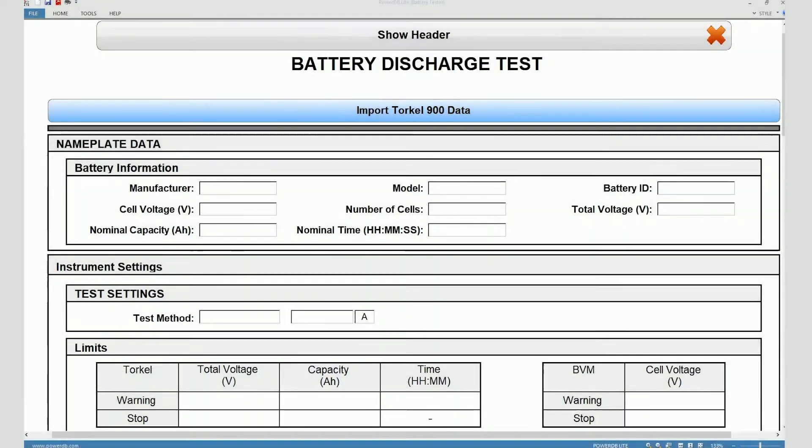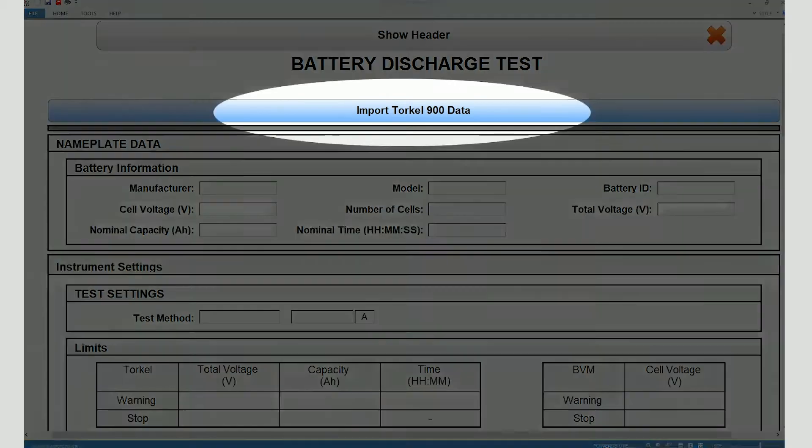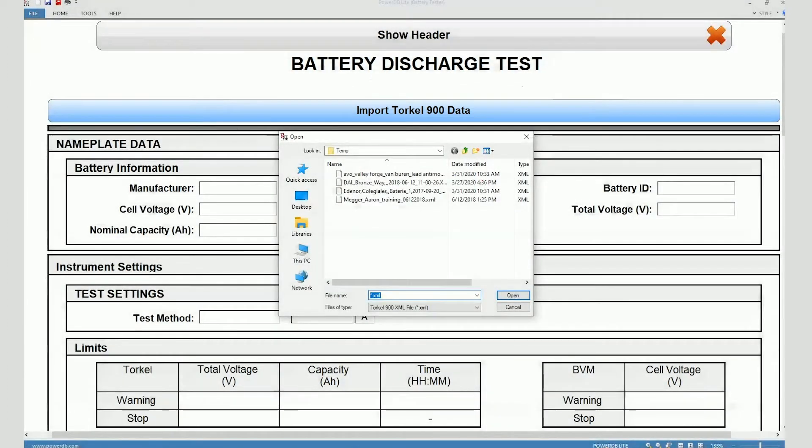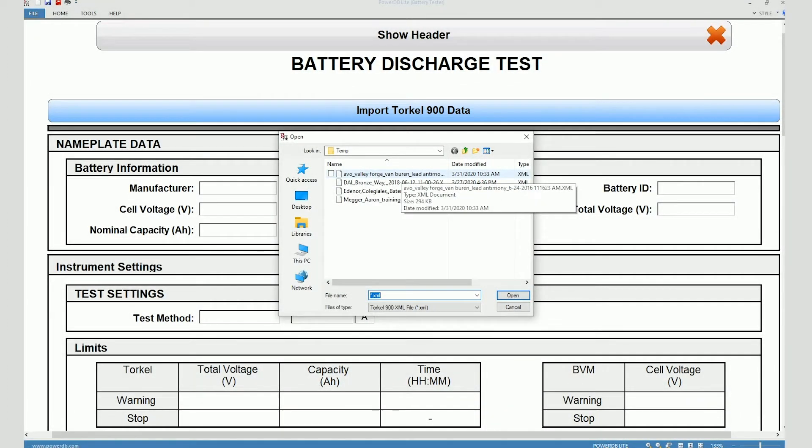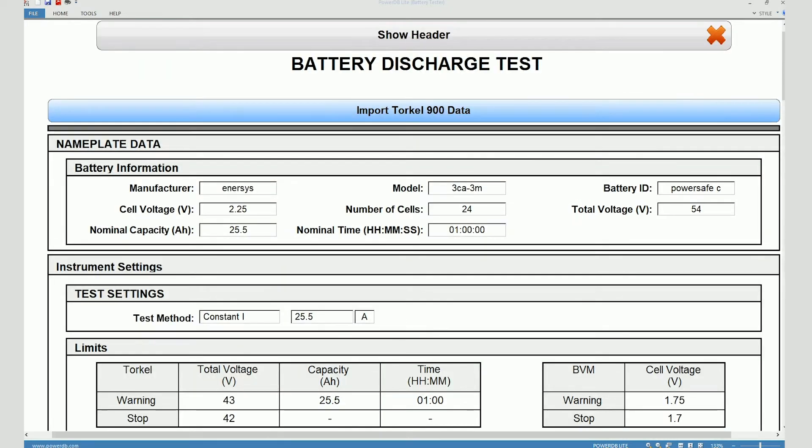When you do that it brings up the battery discharge test form. You will see that the form is blank. What you will do is click on import Torkel 900 data and then select the XML file that you have downloaded from the instrument. In this case I have a few XML files. I'm going to select one of them.